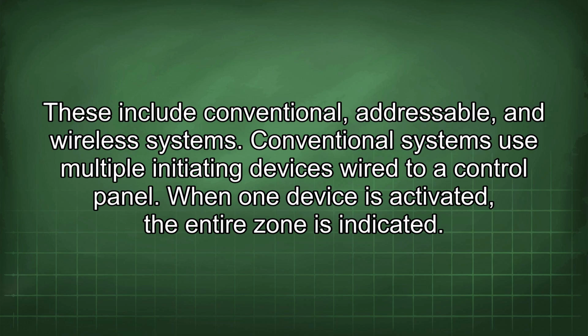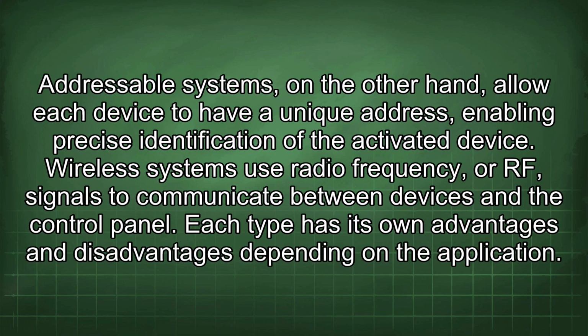Conventional systems use multiple initiating devices wired to a control panel. When one device is activated, the entire zone is indicated. Addressable systems, on the other hand, allow each device to have a unique address, enabling precise identification of the activated device. Wireless systems use radio frequency, or RF, signals to communicate between devices and the control panel. Each type has its own advantages and disadvantages depending on the application.